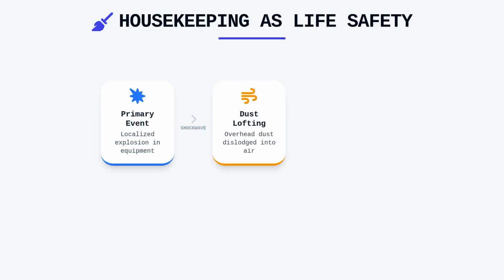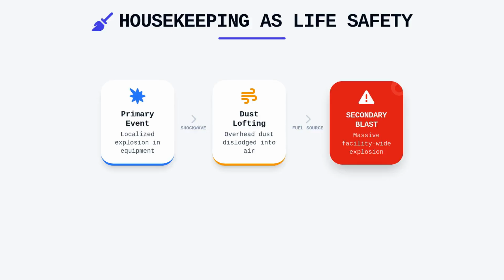Housekeeping is often dismissed as a purely administrative task, but in the context of explosion prevention, it is a critical life safety function. The primary danger in large industrial facilities is not necessarily the initial primary explosion, which may be localized within a piece of equipment, but the subsequent secondary explosion caused by the shock wave dislodging overhead dust. This leads to a domino effect where previously dormant, settled dust is lofted into the air, creating a massive facility-wide fuel source for a much larger blast.